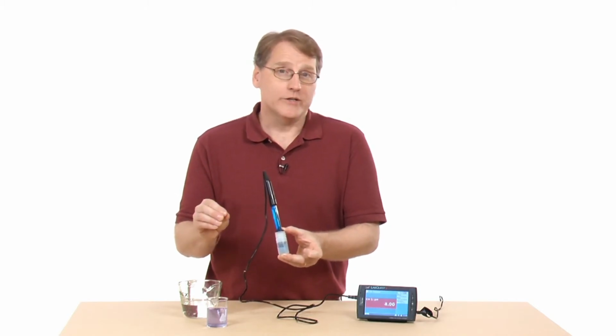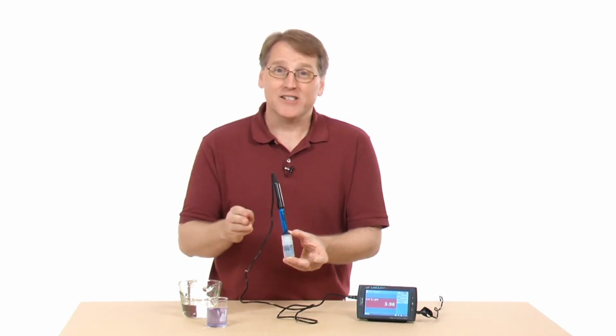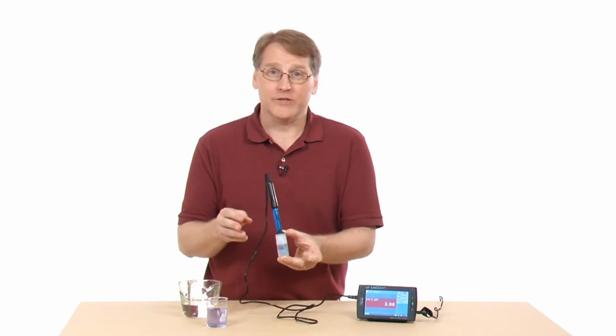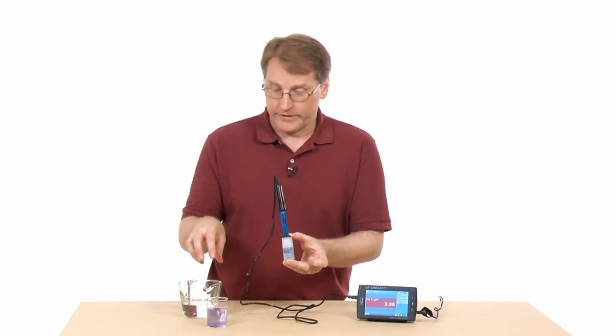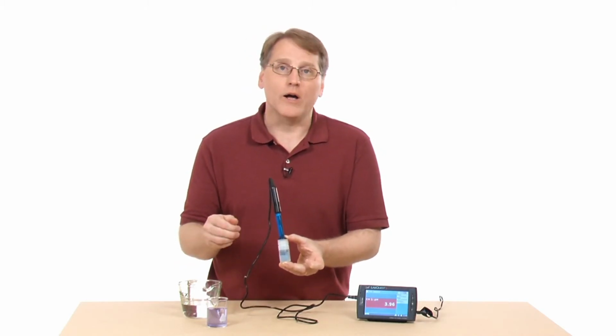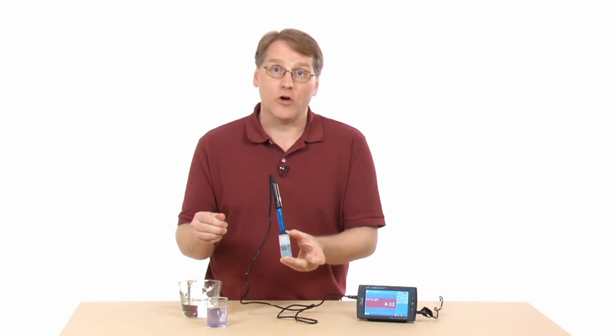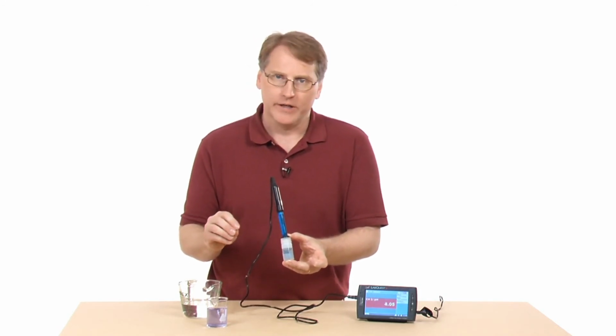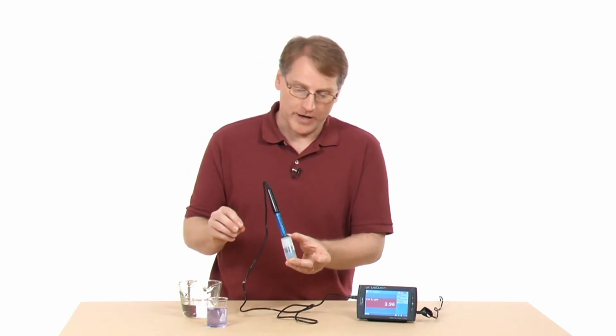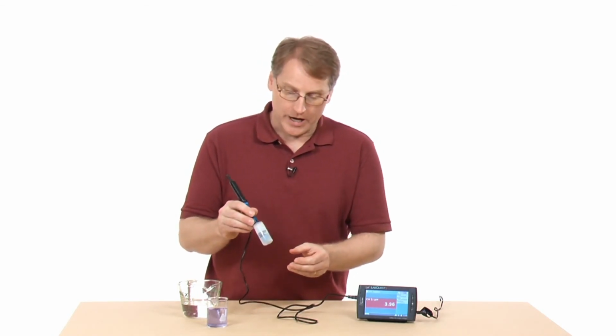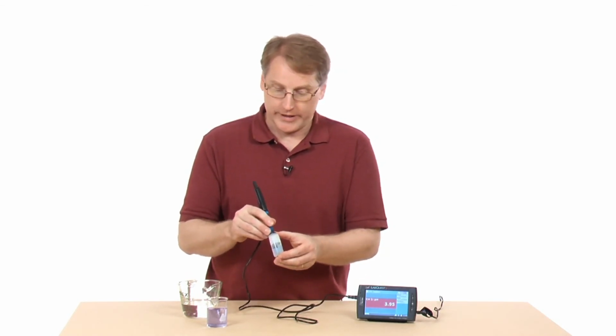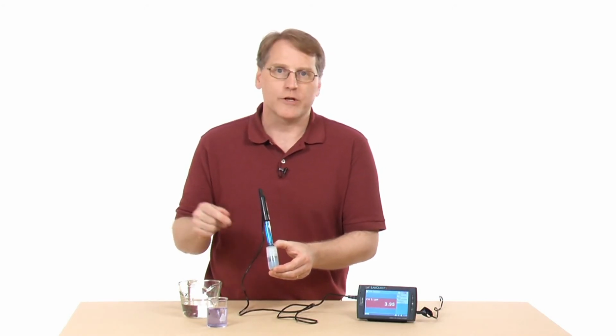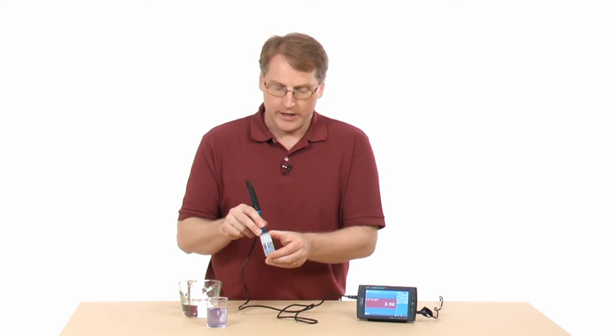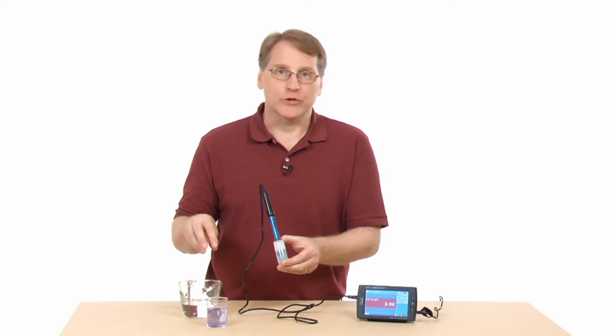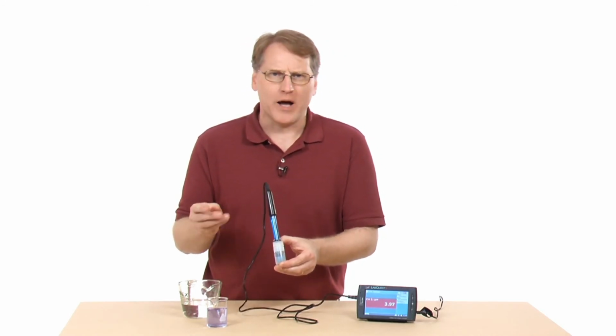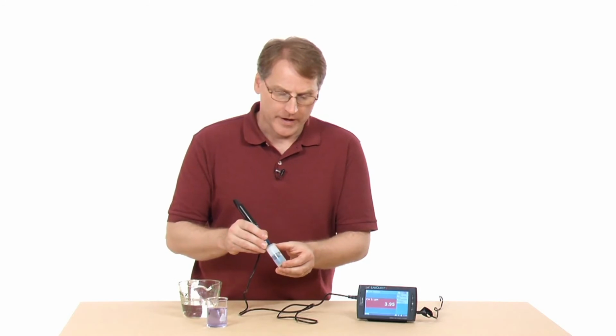Or sometimes they put it into a solution and they find that it's actually slightly acidic because it turns out that maybe the distilled water has been sitting around for a while and you have some carbon dioxide dissolved in that, so you have a weak carbonic acid. And so that's what you might discover there. If you actually wanted to use this in a very soft solution or something without a lot of ions, there's actually something you can add to your solution. It doesn't change the pH, but it provides some ions to make it work there.